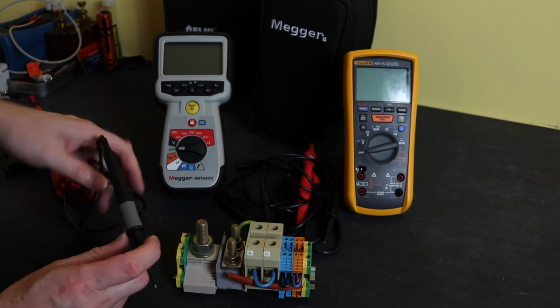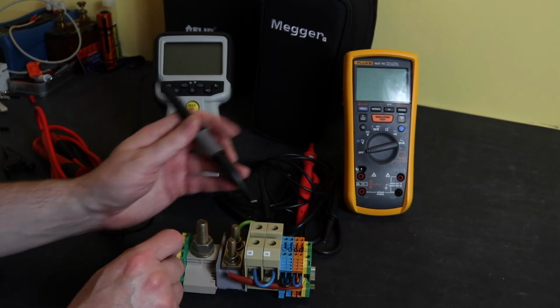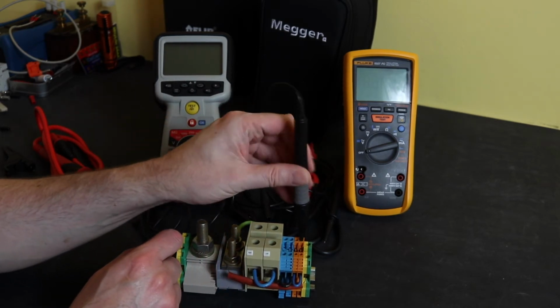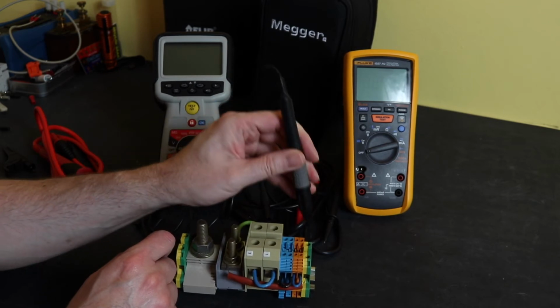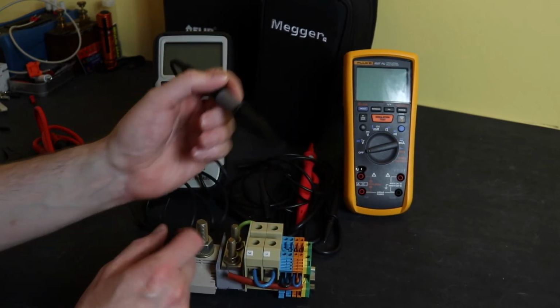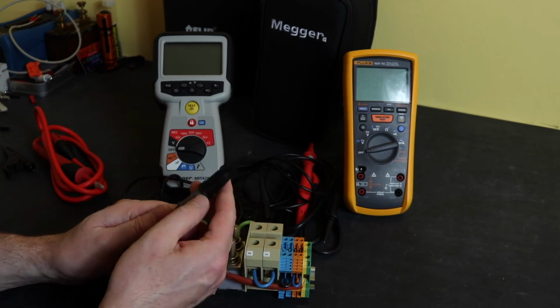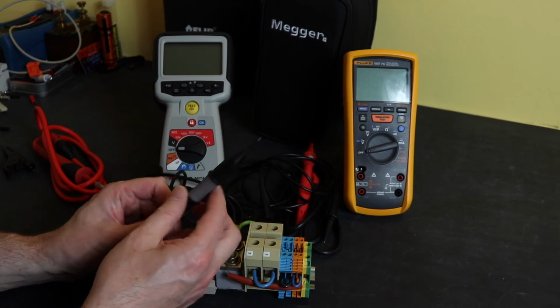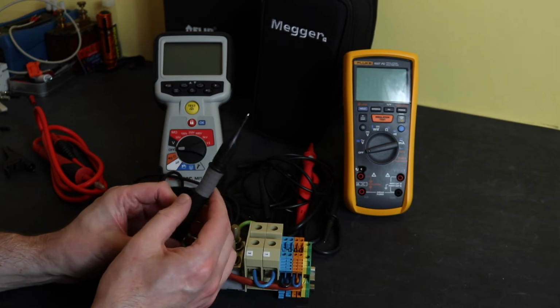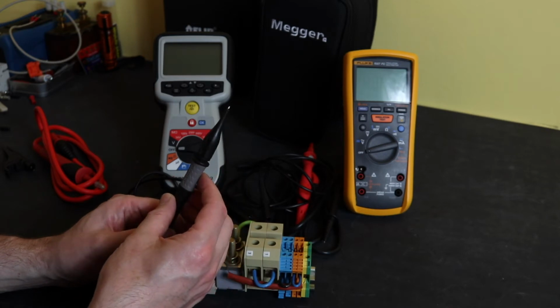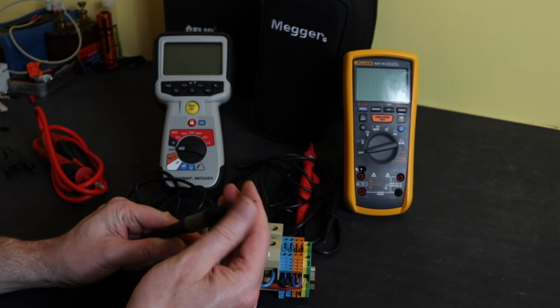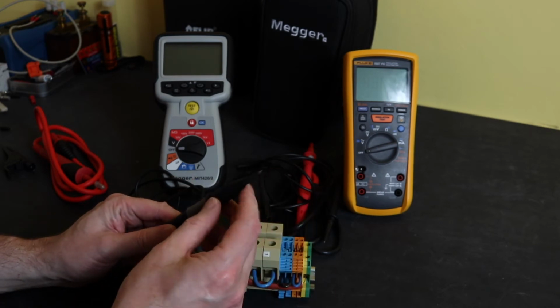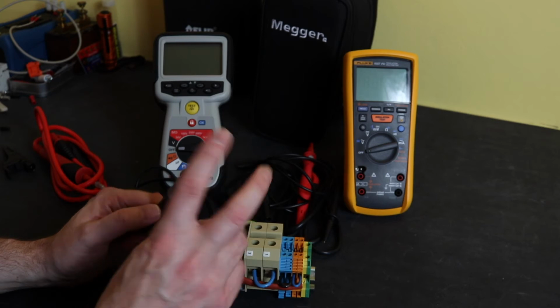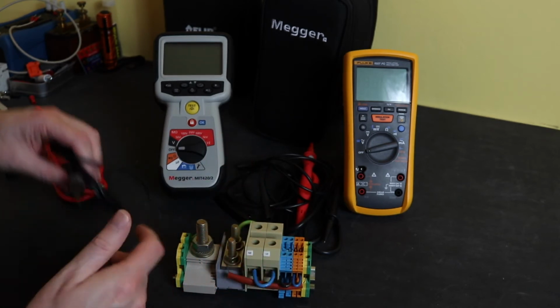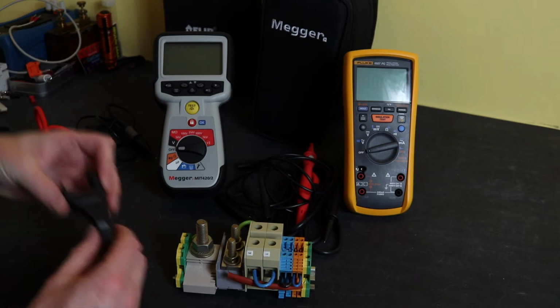In terms of their access to terminals, we've got a 2.5 terminal here. You can see I can get in there and make contact, 4mm, 6mm, 35, no problems. This is probably one of the most refined probe tips I've seen on an insulation tester. Really is very, very sweet. No problems with access to it, and it maintains its GS38 compliance at all times. You can't even remove any of this insulation without a knife or something like that. So yeah, very, very nice lead and probe tip from Megger there.